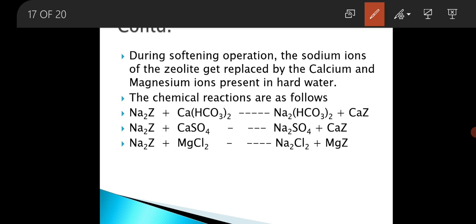The chemical reactions are as follows. When sodium zeolite, that is Na2Z, reacts with calcium bicarbonate — the hardness present in water — it will form Na2(HCO3)2, that is sodium bicarbonate, which does not cause any hardness, and produces calcium zeolite, which is the used zeolite.